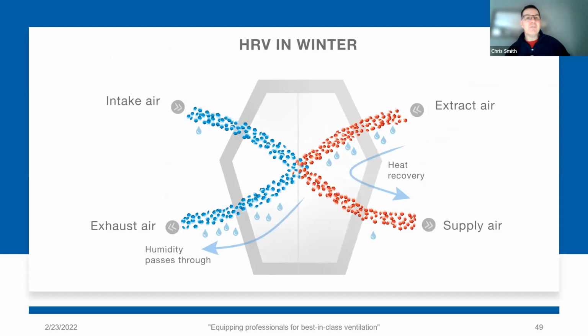If we look at an HRV or heat recovery ventilator in winter, we can see that on the right side of this diagram would be your indoors. On the left side of the diagram is your outdoors. So this is winter, so outdoors is cold, indoors is warm. The extract air starts in the upper right, and it flows through the heat exchanger and is exhausted out of the house on the lower left. The outdoor air starts in the upper left, is cold air outside, flows into the heat exchanger, crosses through, and is delivered to the house on the lower right side of the diagram as supply air.